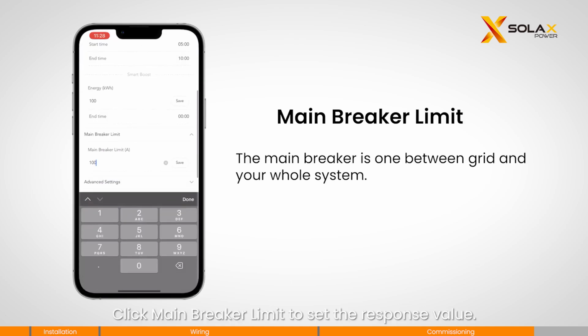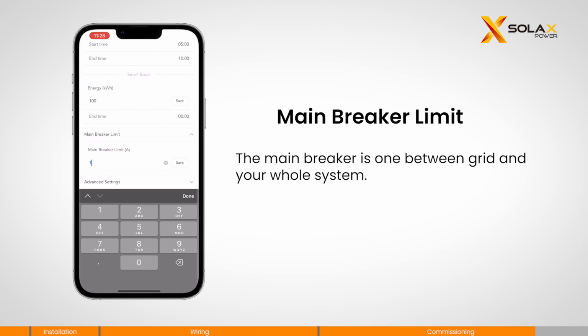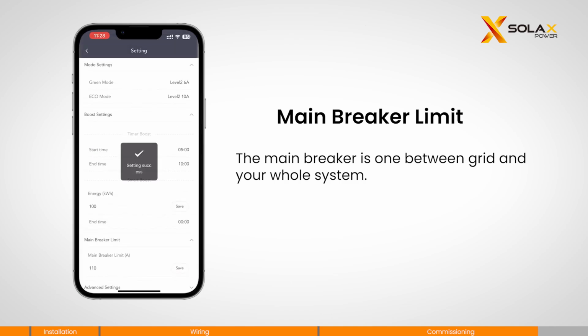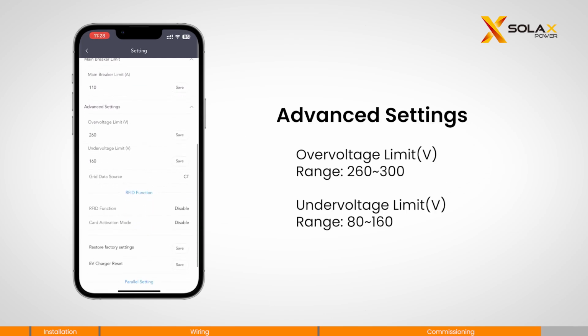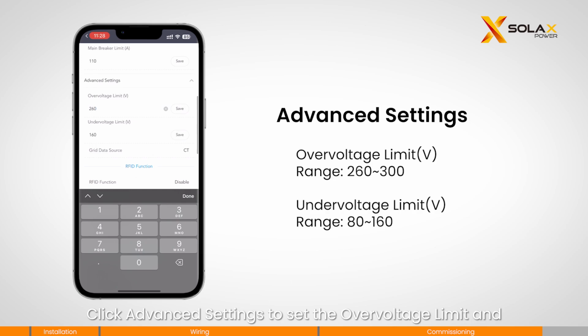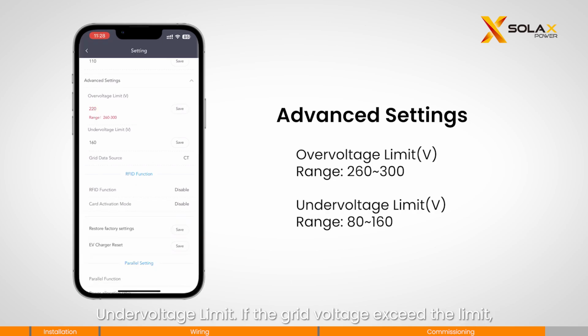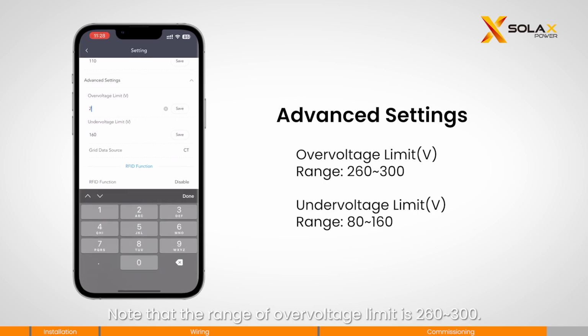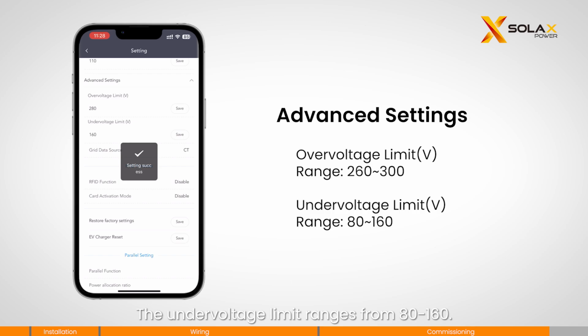Click Main Breaker Limit to set the response value. Click Advanced Settings to set the overvoltage limit and undervoltage limit. If the grid voltage exceeds the limit, the charger will stop work. Note that the range of overvoltage limit is 260-300. The undervoltage limit ranges from 80 to 160.